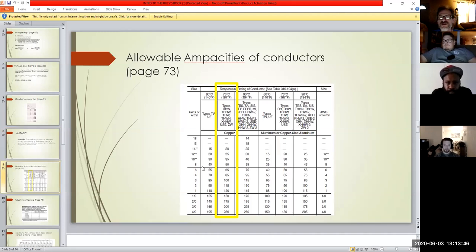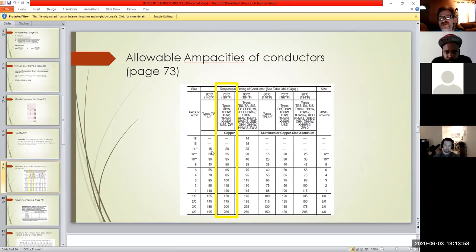When they measure wire sizes, what they look at is ampacity. So what can number 14 run? Number 14 is very typically hooked up to a 15 amp breaker. Number 12, typically a 20 amp breaker. Number 10, a 30 amp breaker. Number 8, a 40 amp. You see how that's going? So on and so on.